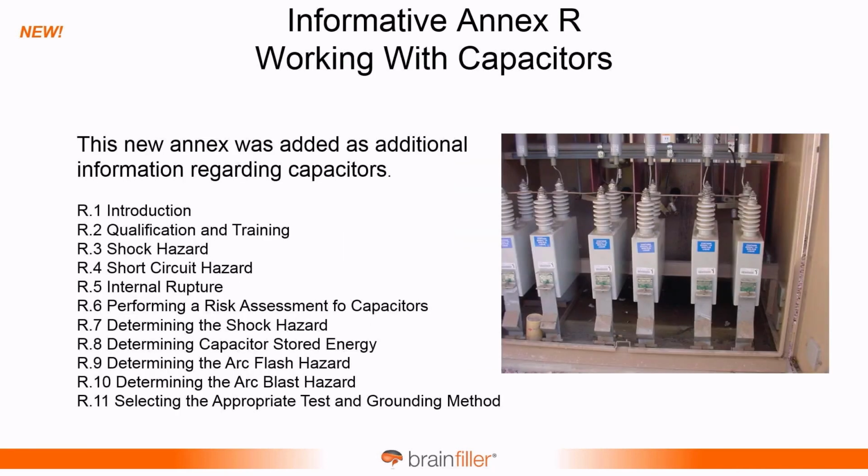We also have another informative annex, Informative Annex R. This is a monumental amount of detail about working with capacitors. This has some great information in it. This has a lot of equations and calculations when it comes to determining the stored energy and the blast hazard. There's actually information in there about a blast hazard relying on some earlier equations.